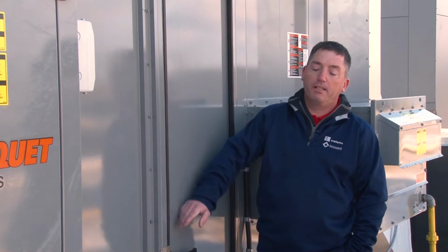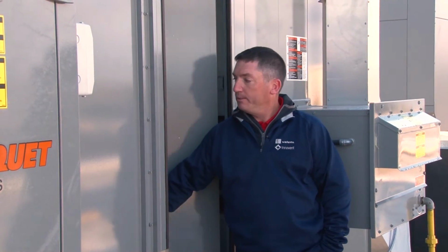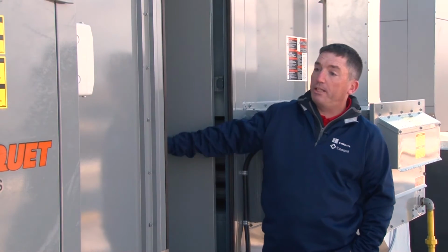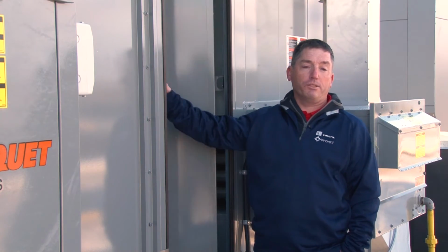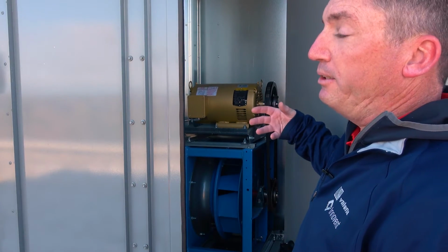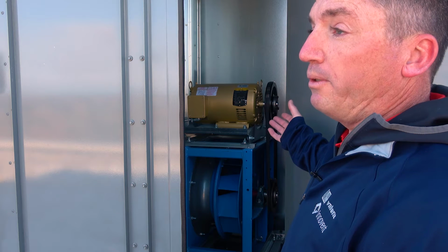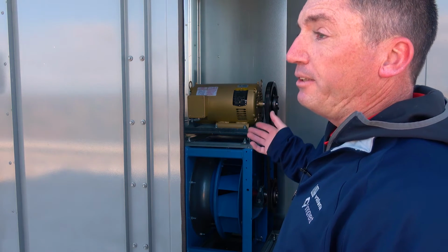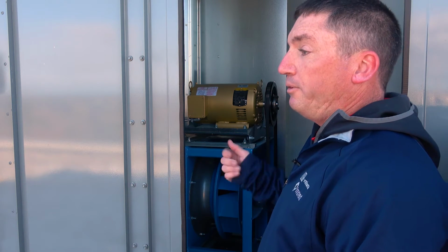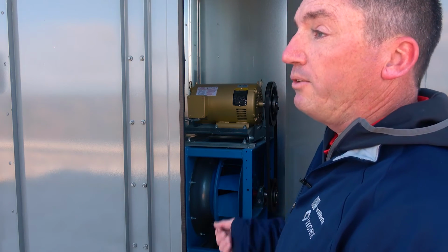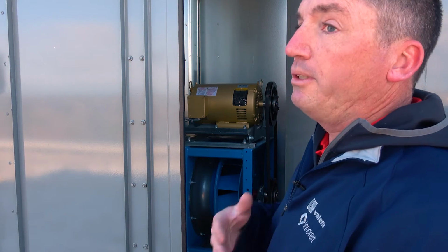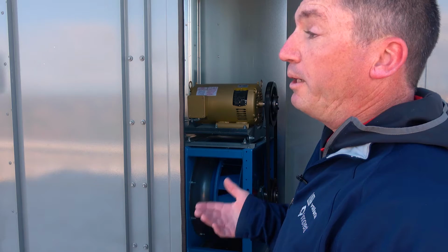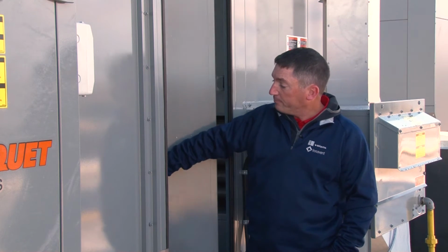This door gives you access to the supply blower. You'll notice that this door opens in because the blower creates a positive pressure, so it's an inward opening door as a safety feature. If the fan was running and you were to walk up to the unit, open the two handles, not realizing it, the door would swing open quite quickly and could injure you.